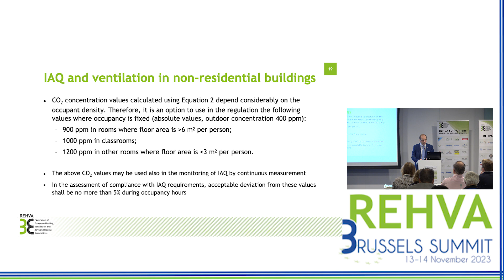And as I said previously, when we speak about residential buildings, it's another approach, where we have very clearly rooms where we need to have clean air supplied as supply air from the ventilation system, or intake from the outer air. So these are living rooms, bedrooms, and we have another category of rooms which are so-called wet and polluted rooms, and from these rooms first this clean air needs to be transferred to the toilets and bathrooms and then extracted from these rooms.